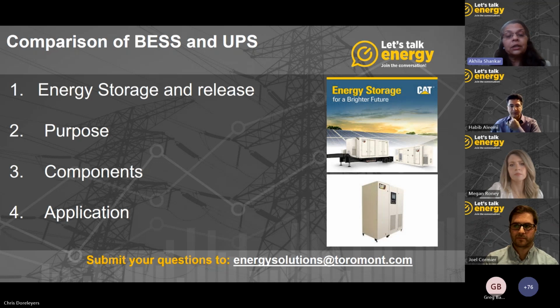Now, if we compare the components, a UPS comprises batteries. It has an inverter to convert DC power to AC. It has surge protection to guard against power spikes. And lastly, it has monitoring and control systems to manage the power flow and battery status. Similarly, a battery energy storage system also comprises high-capacity batteries. It has inverters/converters for managing the flow of electricity to and from the batteries. It has systems to monitor and optimize the battery health and efficiency. But unlike the UPS, a battery energy storage system has additional controls that are required for integration with the grid systems and with renewable energy sources.